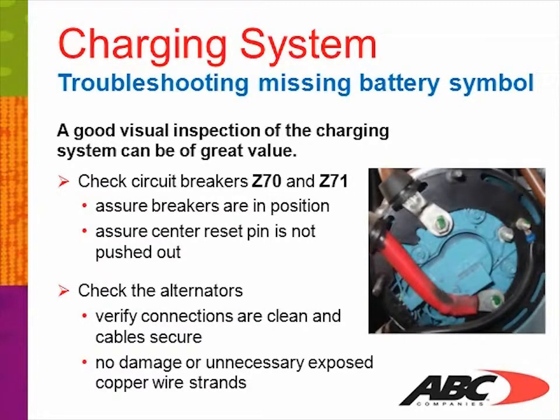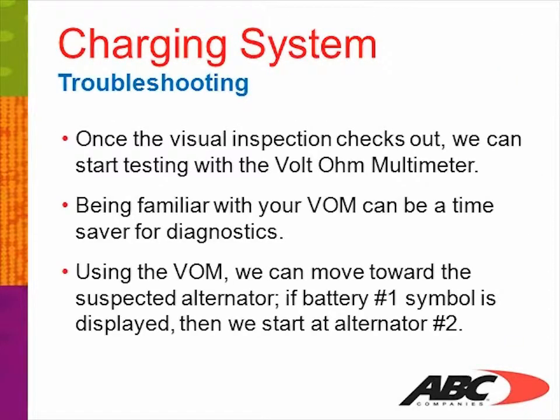Check the alternators. Verify the connections are clean and cables secure, with no damage or unnecessary exposed copper wire strands that would prevent any further issues. Once the visual inspections check out, we can start testing with our Volt Ohm Multimeter. Being familiar with your Volt Ohm meter can be a great time saver for diagnostics. Using the Volt Ohm meter, we can move toward the suspected alternator. If only one battery symbol is displayed, then we start at alternator number 2.